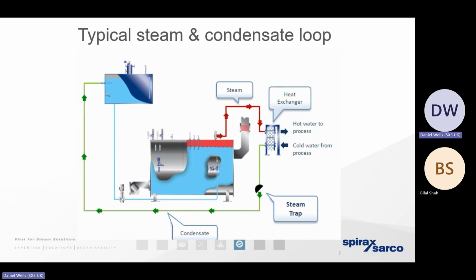So when we're talking about steam, I'm going to call it a gas just for ease. With steam being a gas, it's compressible. So the higher the pressure, the smaller the volume that steam is going to occupy. So if we've got a high pressure in the boiler, we've got two benefits.